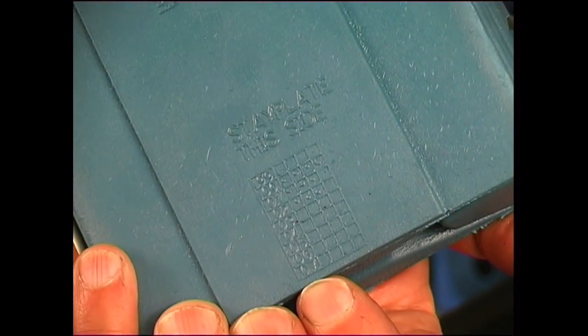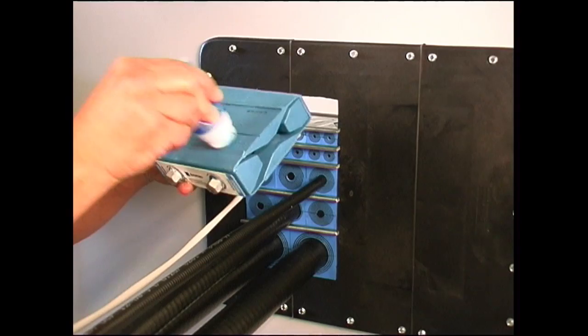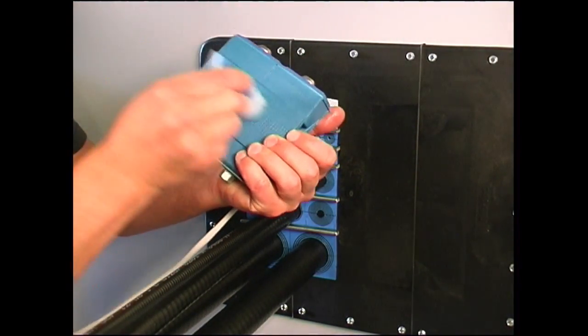Finish the installation with the Roxtec wedge. Make sure the bolts are loose and be sure that the marked side of the wedge is facing the stay plate. Lubricate and insert the wedge.